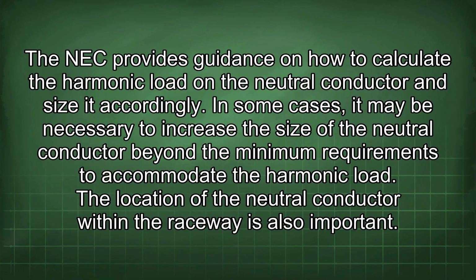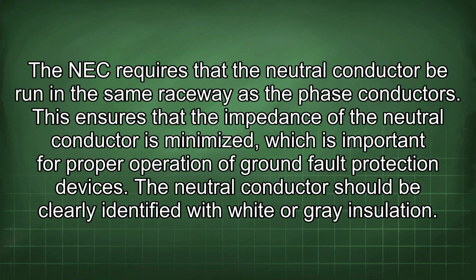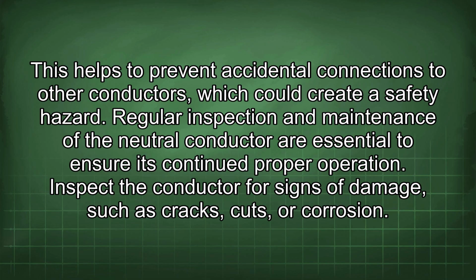accommodate the harmonic load. The location of the neutral conductor within the raceway is also important. The NEC requires that the neutral conductor be run in the same raceway as the phase conductors. This ensures that the impedance of the neutral conductor is minimized, which is important for proper operation of ground fault protection devices. The neutral conductor should be clearly identified with white or gray insulation. This helps to prevent accidental connections to other conductors, which could create a safety hazard.